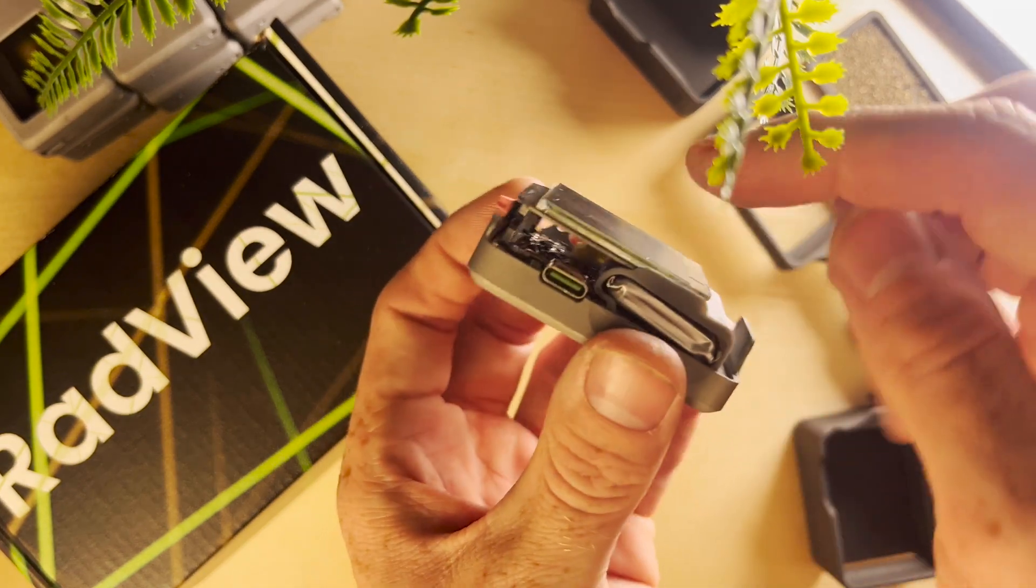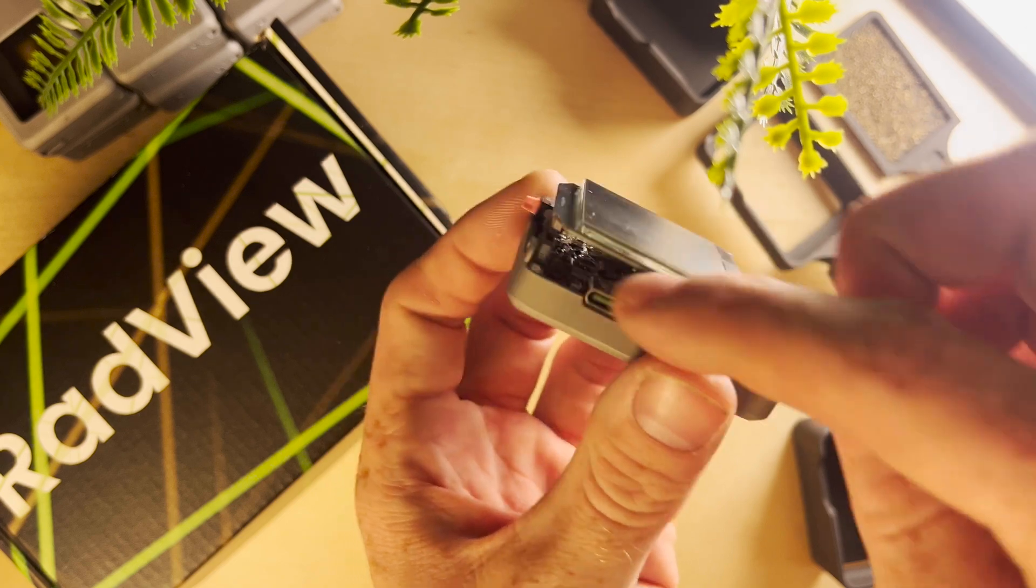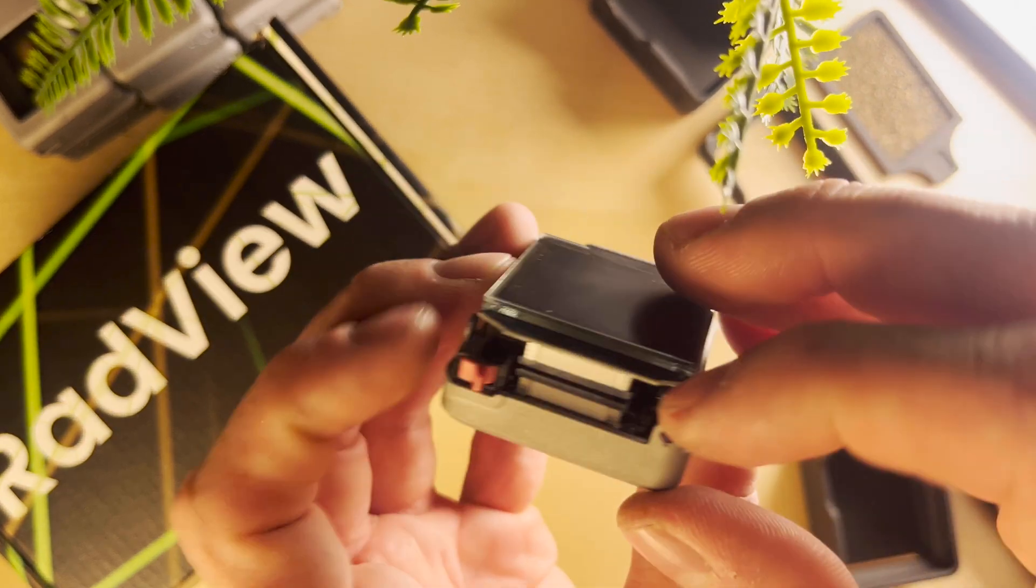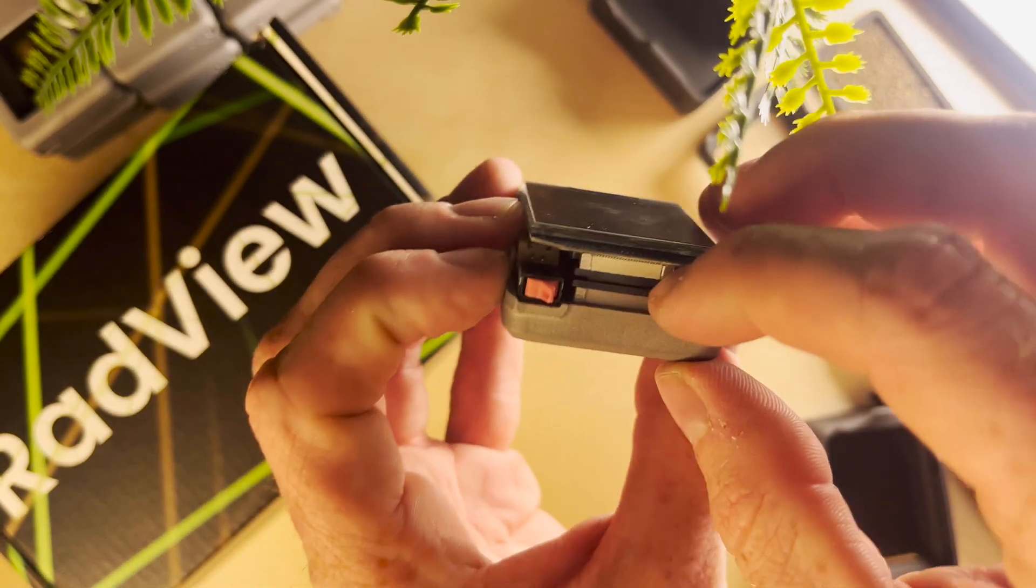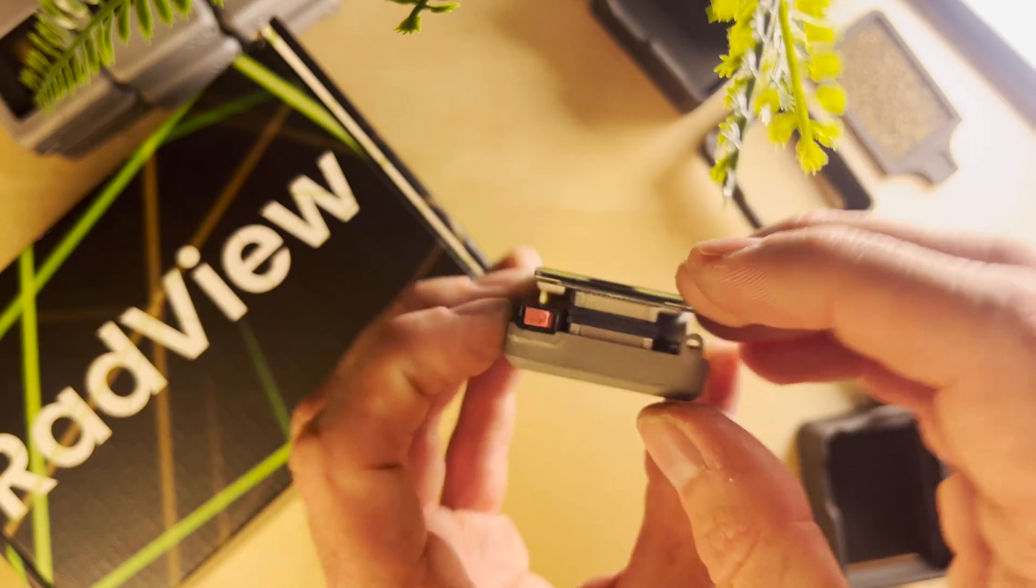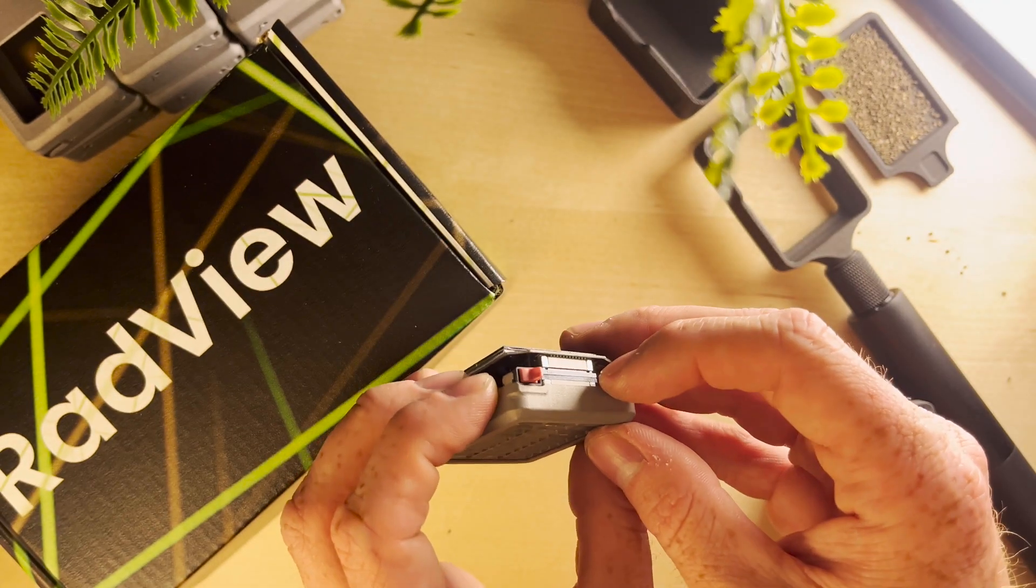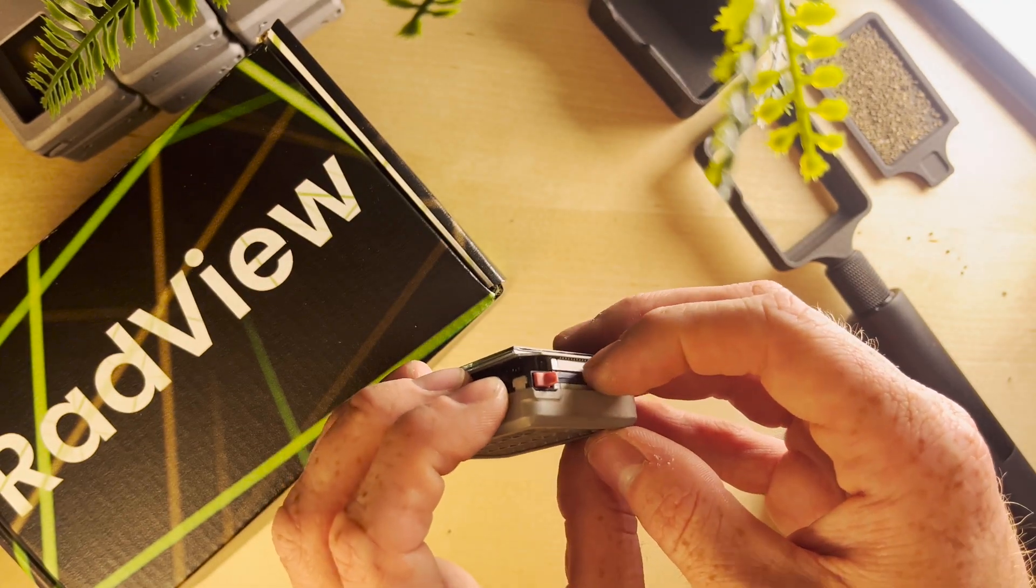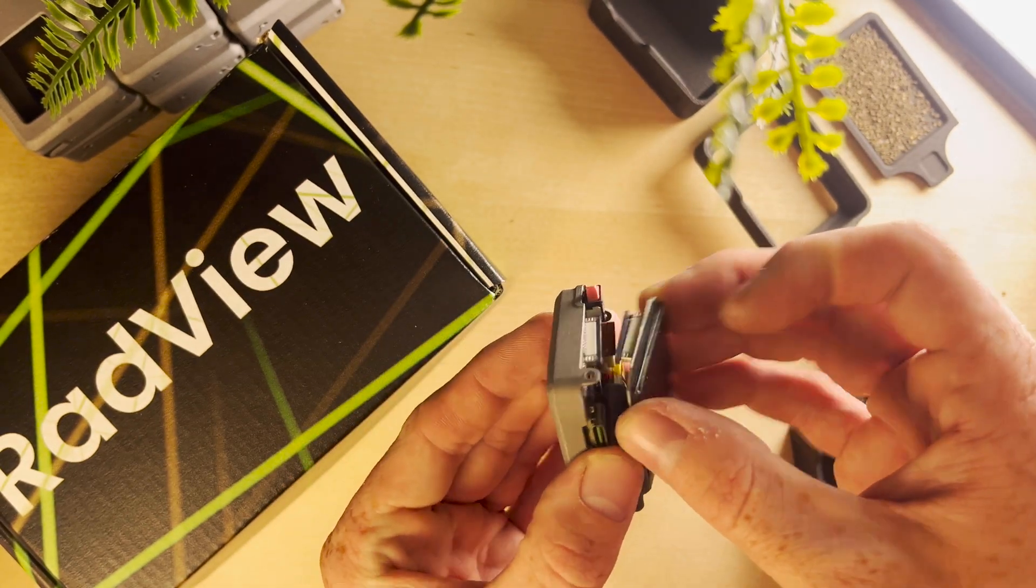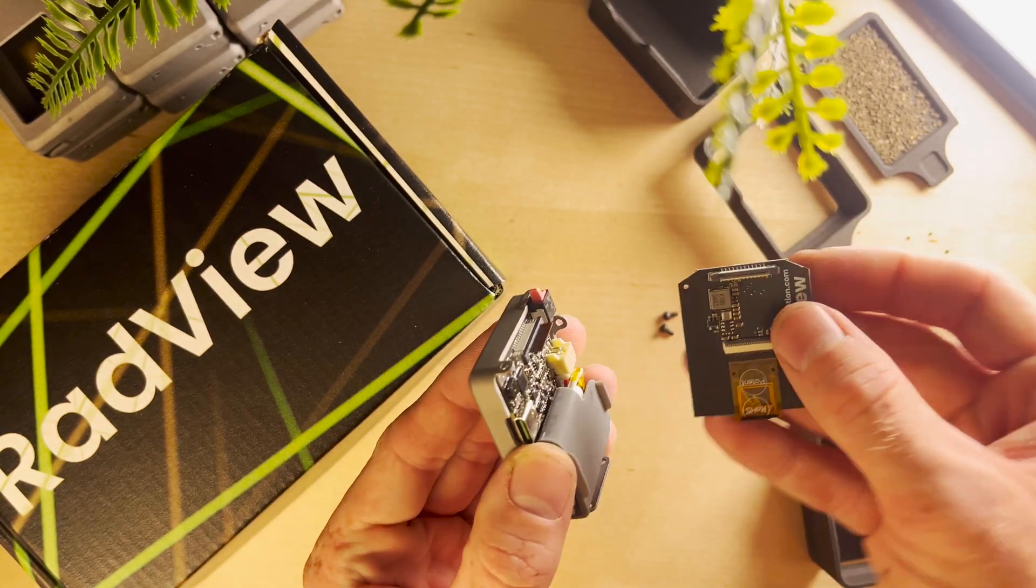Now we have the display and the main board down here. We're going to undo these clips up top, just the top one, and we're going to push it down with our fingernail. You can see here this is unlatched and now you're able to wiggle the screen off.